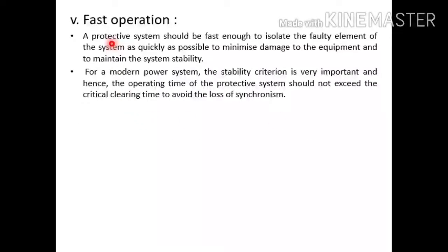Fast operation. A protective system should be fast enough to isolate the faulty element of the system as quickly as possible to minimize the damage in the equipment and to maintain the stability. So the stability criterion is very important, and hence the operating time of the protective system should not exceed the critical clearing time, to avoid the loss of synchronism.